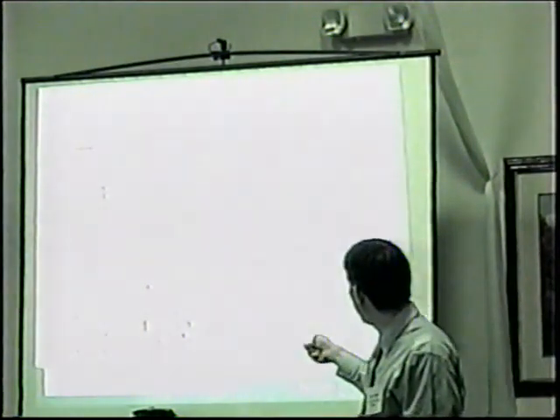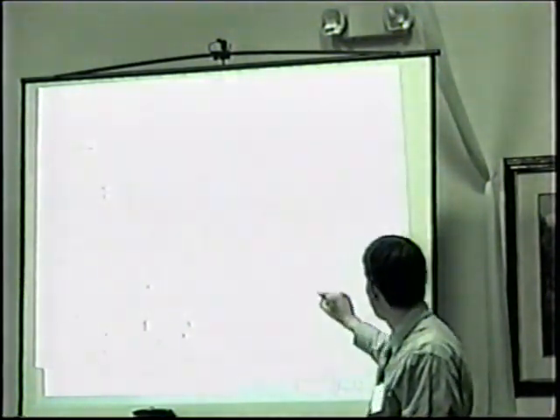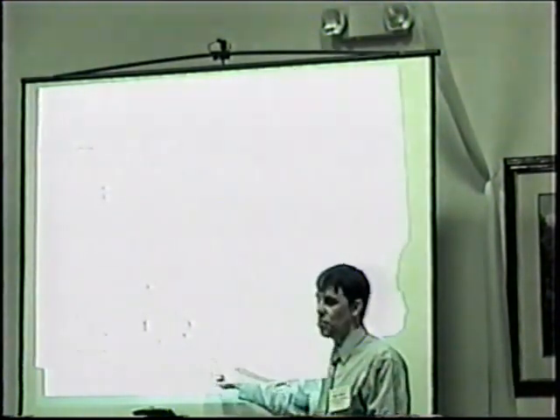And this is sort of where you demonstrate it right in here. And then here's test 74. Test 74, this is just the class 2 curve. And then down here, essentially the same densities are modern sprinklers. And as the orifice sizes go up, holding the density standard at 375, the number of heads you operate goes down. Because the sprinklers are better, we understand how to use them better, we understand the importance of those parameters. The other thing is that when you look at that, as you have relatively minor increases in the discharge density, the number of heads you expect to operate goes down tremendously.